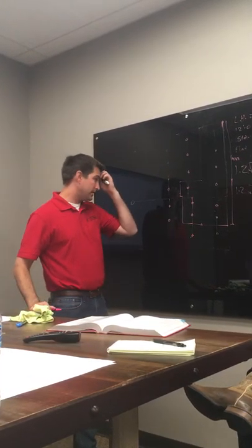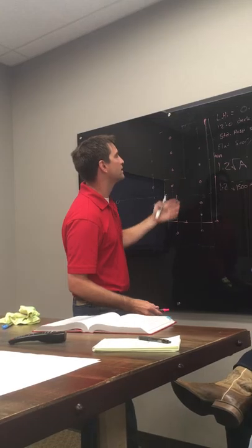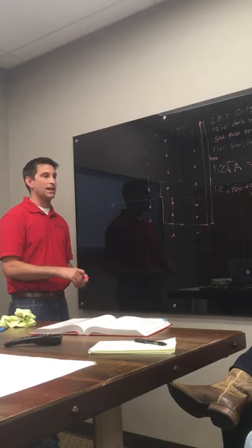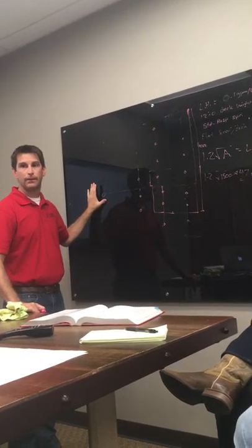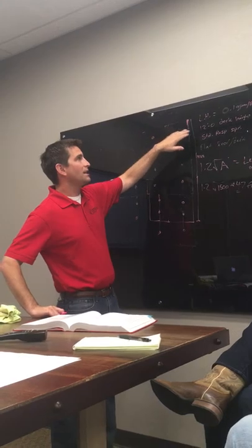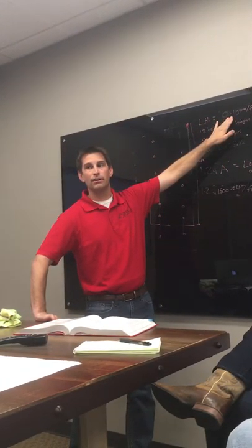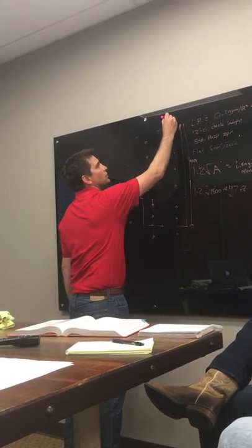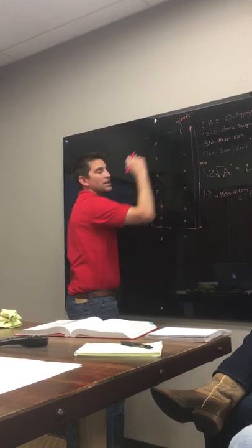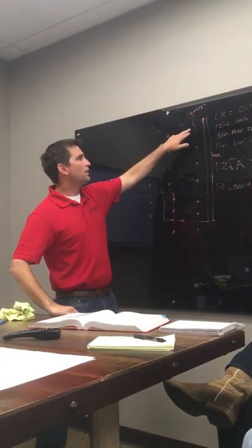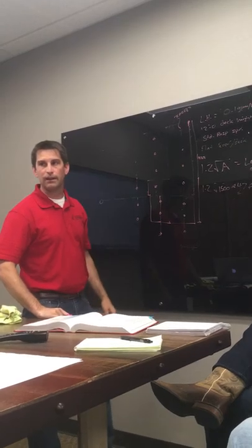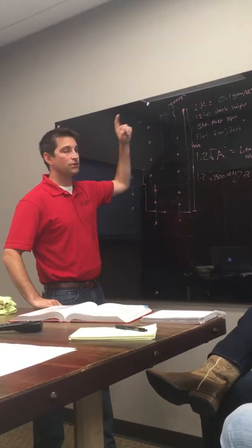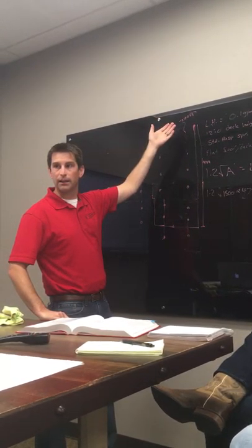But here's the thing, and this might be hard to explain with just this: the way calculations work in your fire sprinklers is it's a demand calc. We're saying I have a known water supply, and at the worst case I have to get at least this amount of water, this density on the ground. So for instance, let's say this sprinkler is spaced 200 square foot, which is the protection area of that sprinkler. If it's 200 square feet and I have to get 0.1 gallons a minute per square foot on the ground, I have a density of 0.1 and I know the head covers 200 square feet, how much water do I need to flow out of the head?